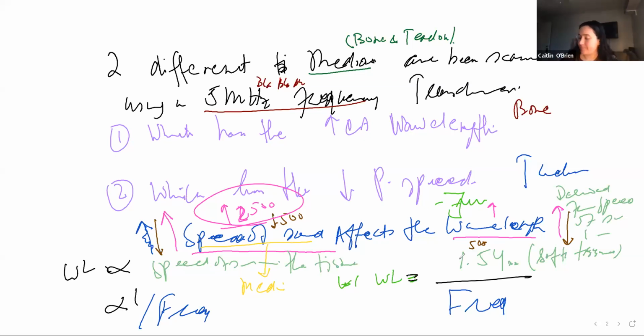And in the middle, we had this number here, 1.54, but this is only going to be applicable to soft tissue. Where did we get this 1.54? It is derived from the speed of sound in the soft tissue. But if you go to faster tissues, you will replace this 1.54 here by just the number of the speed of sound in millimeters in that tissue. Or the other way around.